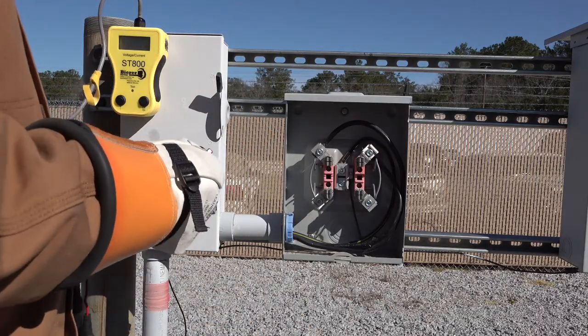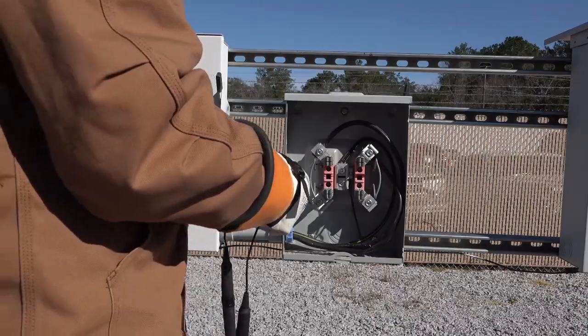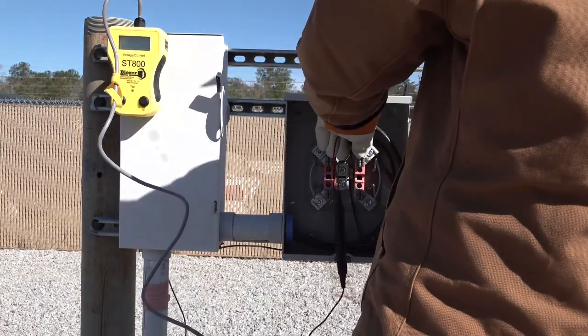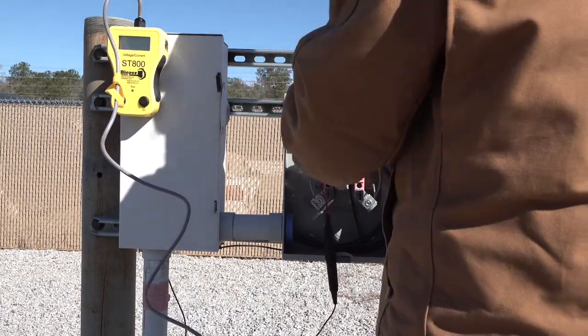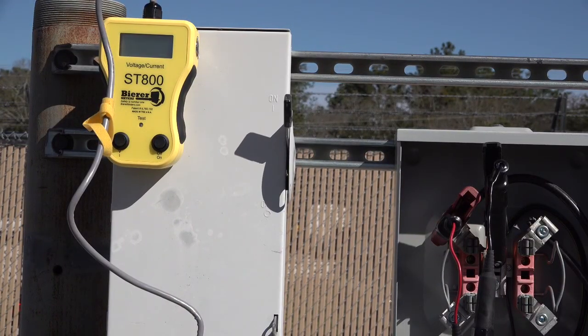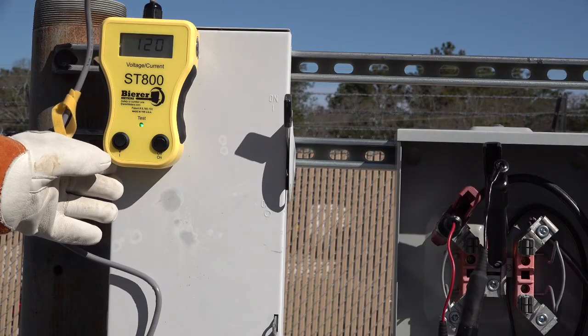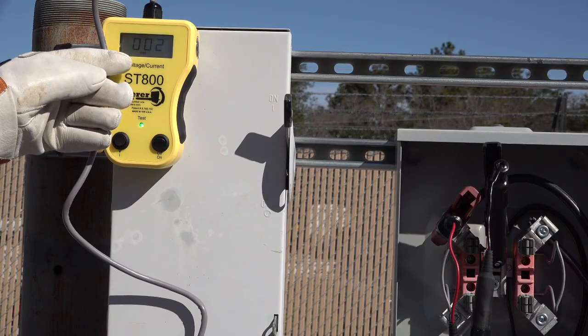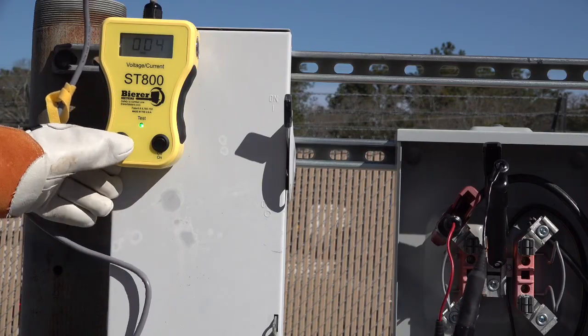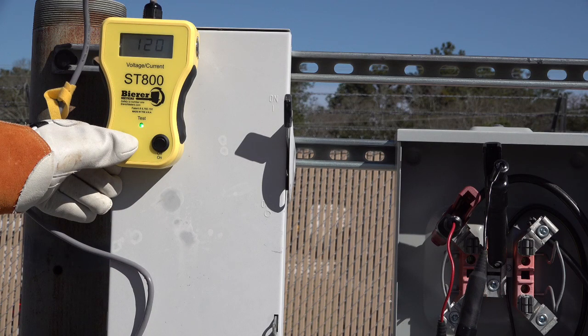So let's begin our first demonstration by connecting the clamps to this meter base and turning the device on. Once all of our connections have been made, you will notice that the black conductor is connected to the neutral and the red conductor is connected to one of our hots in the meter base. We should now turn the device on in the V position. The V position will verify that neither the neutral nor the hot that we have it connected to is open, as demonstrated here by reading 120 volts.